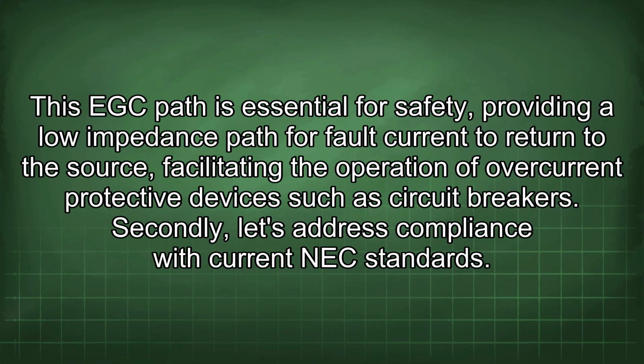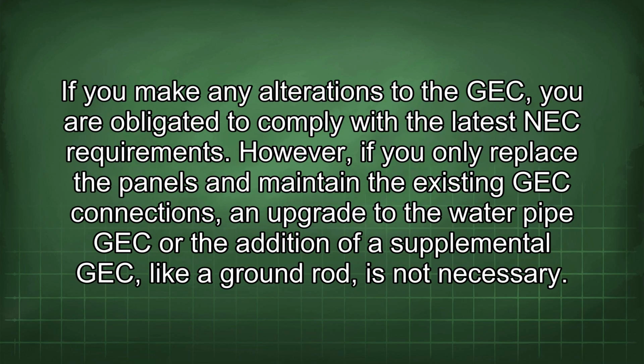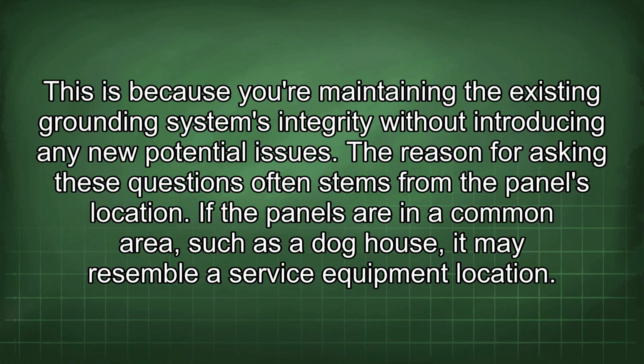Secondly, let's address compliance with current NEC standards. If you make any alterations to the GEC, you are obligated to comply with the latest NEC requirements. However, if you only replace the panels and maintain the existing GEC connections, an upgrade to the water pipe GEC or the addition of a supplemental GEC like a ground rod is not necessary. This is because you are maintaining the existing grounding system's integrity without introducing any new potential issues.